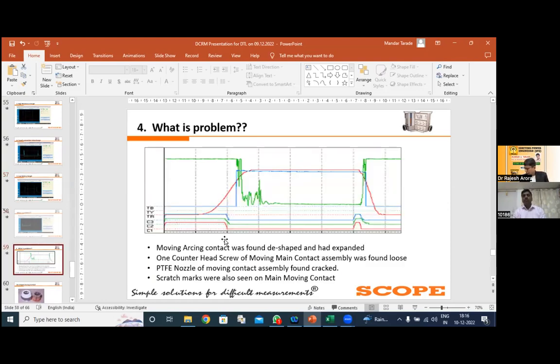Now moving further, here if you see, this is the classic case study. Your arcing contacts won't get stabilized and it will not give you the correct behavior of the arcing contacts. During analysis, diagnostics or preventive maintenance, we came to know that the moving contacts were found de-shaped and had expanded. Also, one of the counter-head screws of the moving contacts assembly was found loose, and because of that, it affects the results.